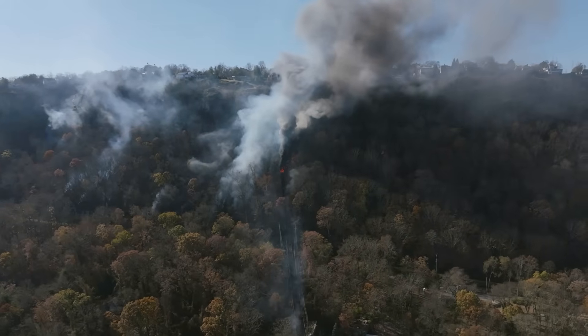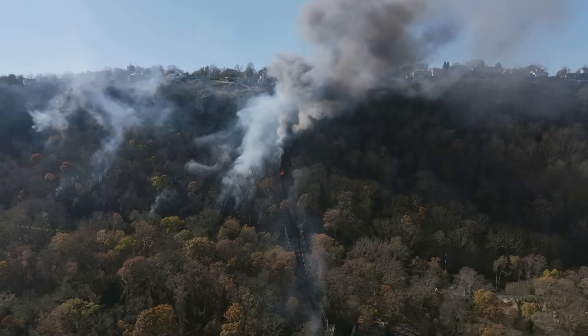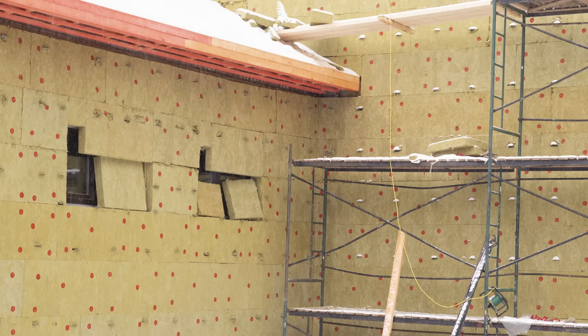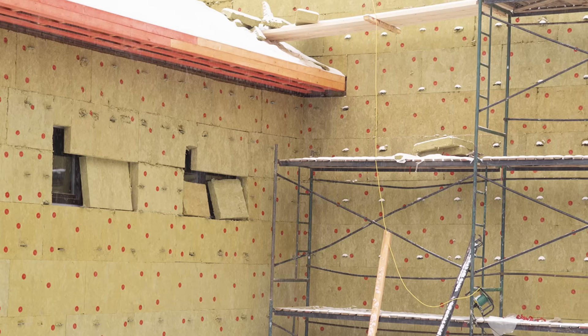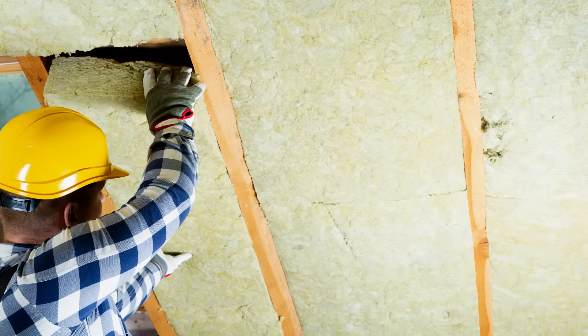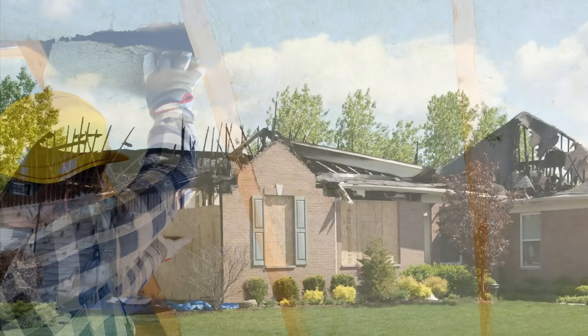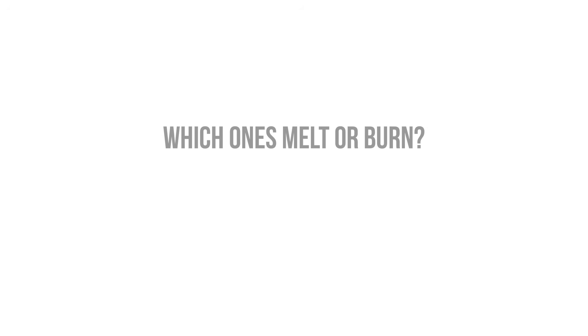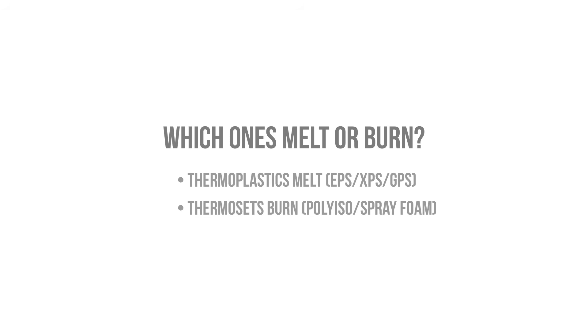Wildfire zones also drive the insulation specifications of many projects. You need to specify insulations that won't burn or melt. Exterior mineral wool is highly recommended for fire protection — it's basically a fire blanket around the entire building, as it's non-combustible and has a very high melting point. Interior rock wool or fiberglass is also highly recommended in the cavities so that fire doesn't easily travel within the framing. Avoid foam products in these regions, as foam burns hot and smokes. Thermoplastics like polystyrene melt, while thermosets like Polyiso and closed-cell spray polyurethane foam burn.